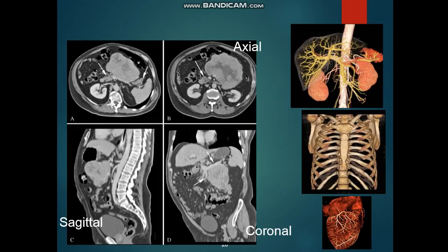Detectors on the exit side of the patient record the X-ray exiting the section of the patient's body being irradiated as an X-ray snapshot at one position of the source of X-rays. Many different snapshots or angles are collected during one complete rotation. The data are sent to a computer to reconstruct all of the individual snapshots into a cross-sectional image of the internal organs and tissues for each complete rotation of the source of X-rays.